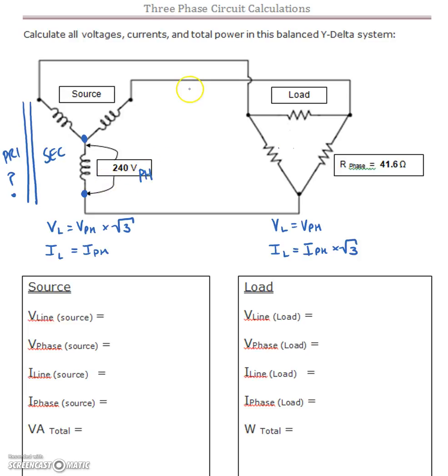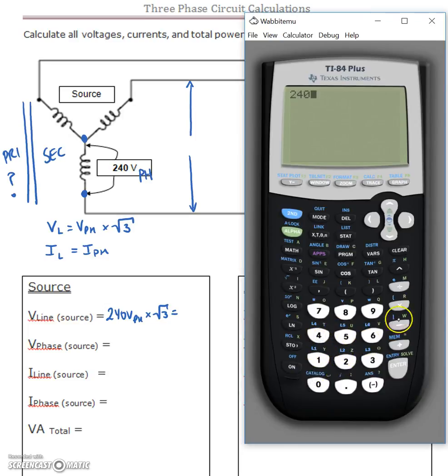We can see that the line voltage would be from here to here. And that line voltage is obviously greater than our phase voltage, and it's greater by root three. So we're going to take our phase voltage of 240 volts, multiply that by root three. And we already know that number, but let's just double check with the calculator. So we've got 240 times the square root of three gives us 415.69. I'm going to round that up to 416 just so we have standard voltages going through.